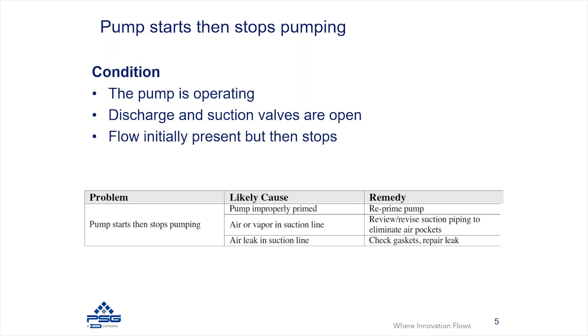You might also need to look at the suction piping to make sure there is no area that would allow an accumulation of air sizable enough to cause the pump to drop out of prime when it's sitting idle. You may need to do some revision to your suction line.